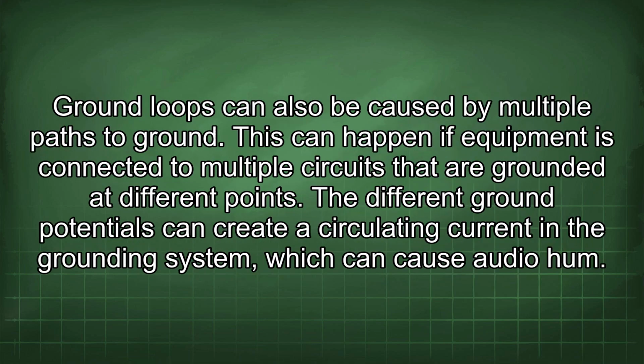Ground loops can also be caused by multiple paths to ground. This can happen if equipment is connected to multiple circuits that are grounded at different points. The different ground potentials can create a circulating current in the grounding system, which can cause audio hum.